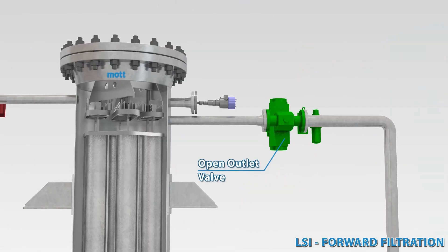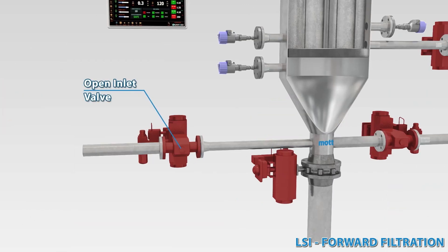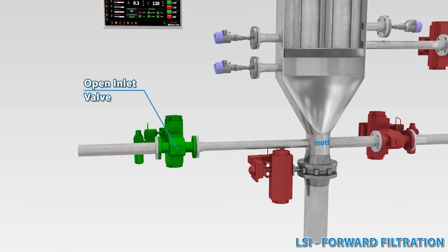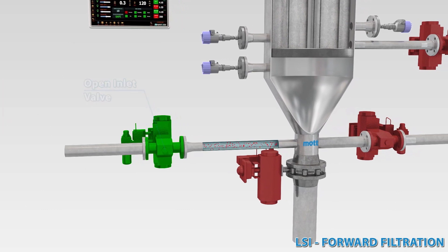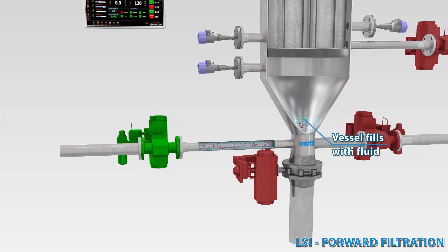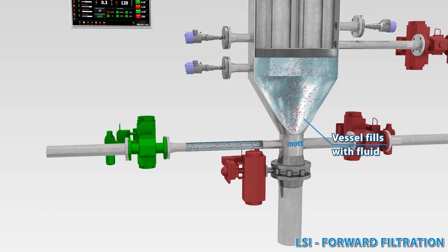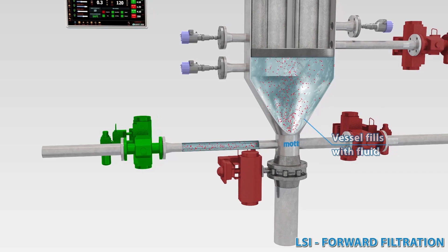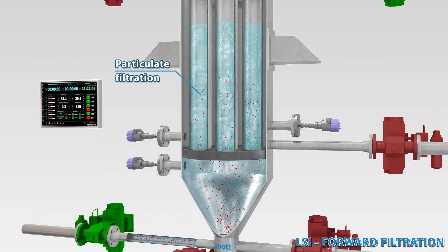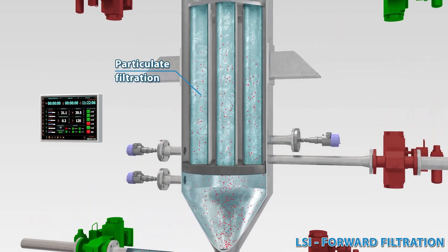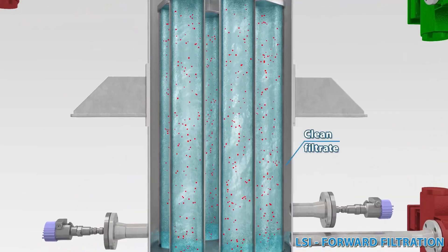Filtration begins by opening the process outlet and inlet to the filter. During online filtration, process fluid enters the heel of the filter vessel. This fluid travels up the length of the filter elements, then permeates through the porous metal media.